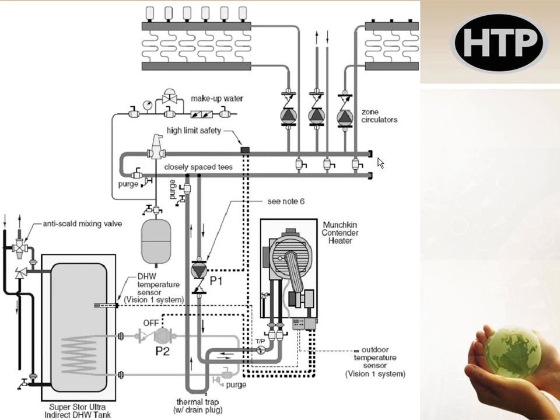What happens with these condensing boilers, with these stainless steel heat exchangers, they have fairly small passageways to shove the water through. So it's good because we get more surface area, we have less water to hold in the boiler. The downside of it, though, is it takes more energy to pump through that. So we typically can't take an old cast iron boiler out that just had one large primary loop for the whole building and drop a condensing boiler in its place without changing some piping. So I've got to change it to primary, secondary piping, and that's a whole other topic in itself. But you get the basic idea here.